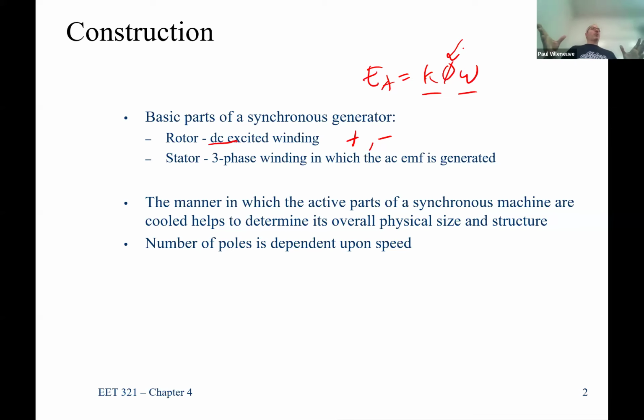Because remember, power equals torque times omega. If we drop the speed in half, but we want the same power output, we have to double the torque. So now you need a lot beefier equipment because you're handling two to four times whatever the value of the torque is. So you really need to be aware of what's happening in terms of that. So our mechanical engineering friends, they need to worry about all that stuff. They'll take care of that.